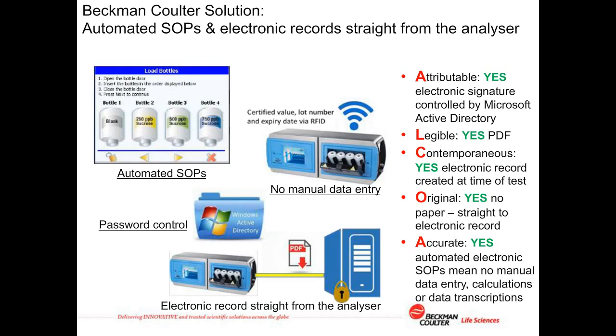Yeah, okay. So as part of the standard validation package, and of course you may wish to add to this, each site has its own rules and regulations that it follows. But as standard, the analyzer validation package that we carry out by our service organization validates that the data exported over Ethernet in PDF format to the customer's server matches the data that's actually on the analyzer. So we do an export and then we check that the data matches to make sure that we've validated that this export, one, works, and two, is accurate to the original analysis.